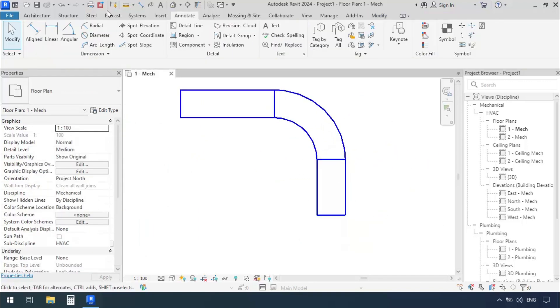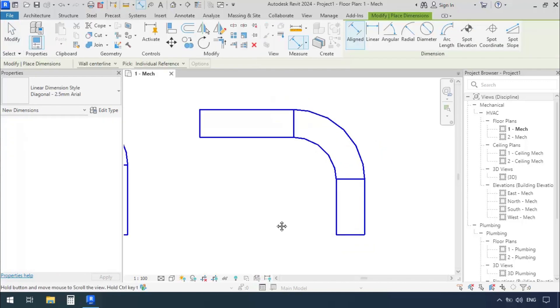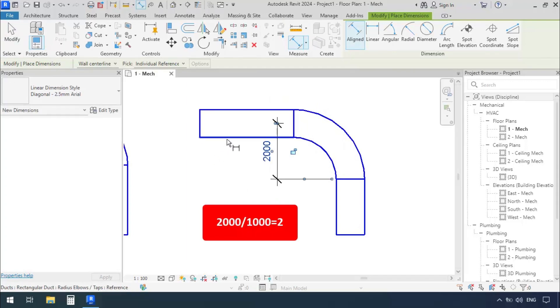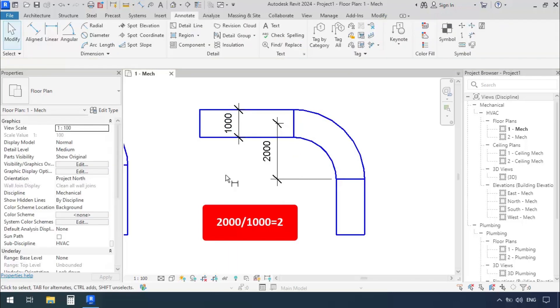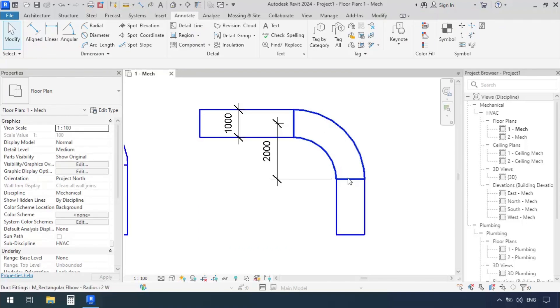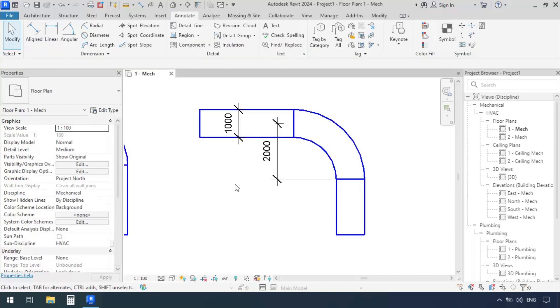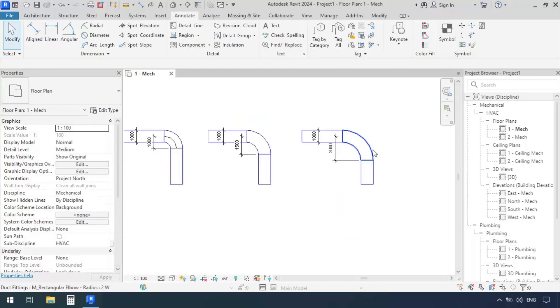In the next and last one, we can guess what's going to happen. Our radius should be 2000. And yes, there it is. The width was 1000. So 2000 divided by 1000 equals 2, meaning the radius of our elbow is 2 times the width. It's 2W, just like what it says here.